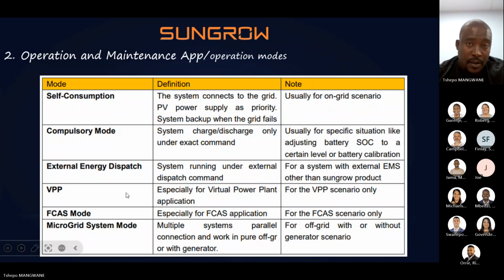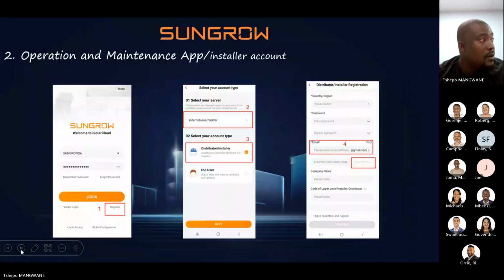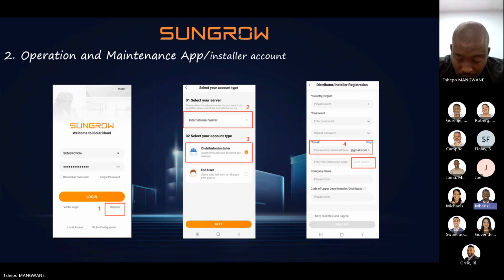Are we all good here? Yeah, all good. So for our system mode in South Africa, we focus on self-consumption, compulsory mode, microgrid system mode. Actually, sorry, I just wanted to ask on the generator side, can we start and stop the generator? Yes, hard start, hard stop the generator. And then communication, let's say it's a deep sea generator, can we connect it directly, or is it more of a signal? It's a signal on the dry contact. So it has to go to the generator controller side.